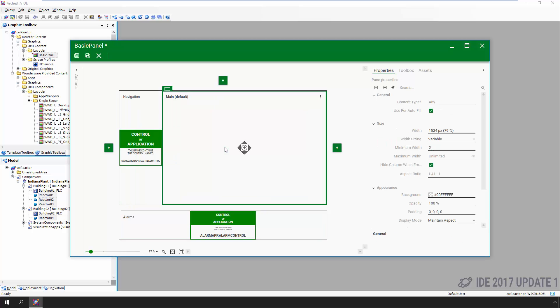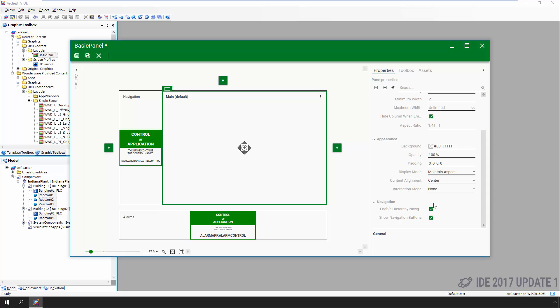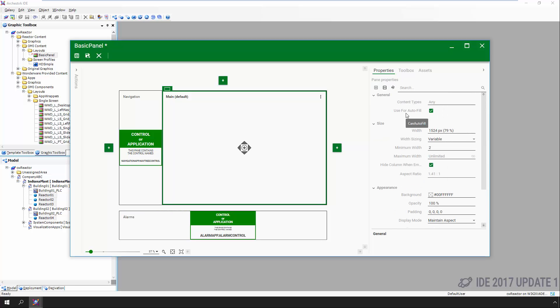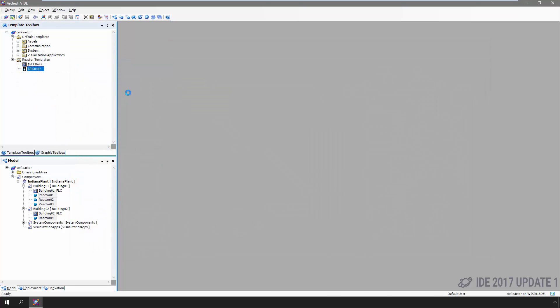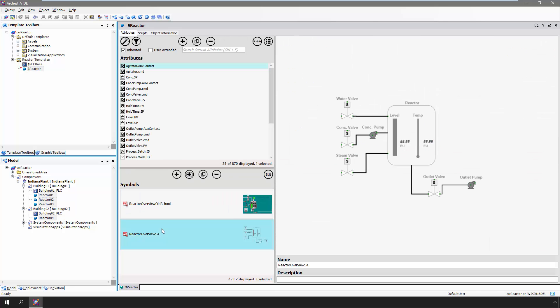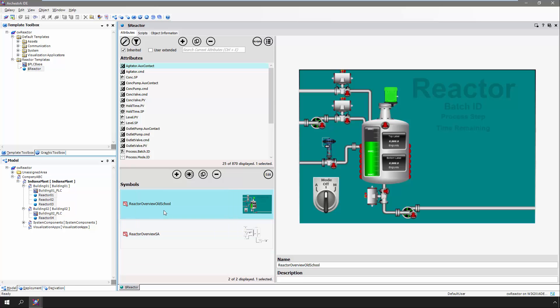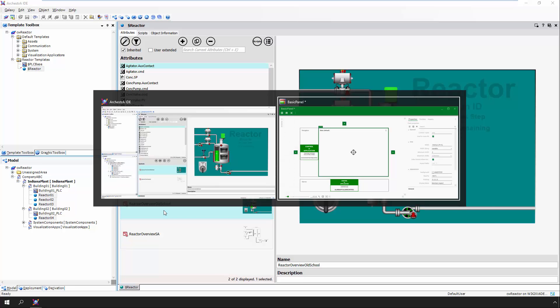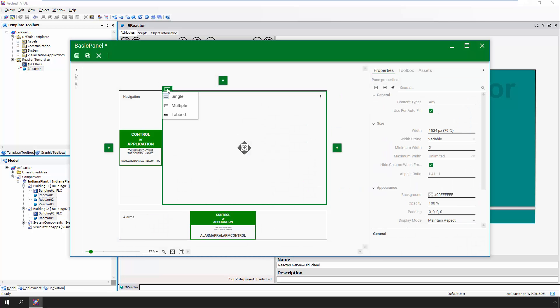Finally, we're ready to configure the main content area. We want the graphics associated with the area or equipment the user has selected in the navigation panel to be displayed here. We don't really need to change anything — by default, panels are set to do what's called auto fill, which means it's going to automatically fill in the appropriate content based on what the user has selected. However, one thing we do need to do is enable the panel to show multiple graphics, since our reactor objects had two graphics associated with them. We accomplish this by clicking on the tab icon for the panel and selecting the option for multiple.